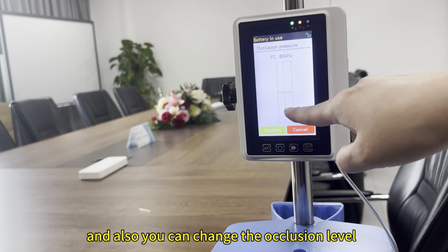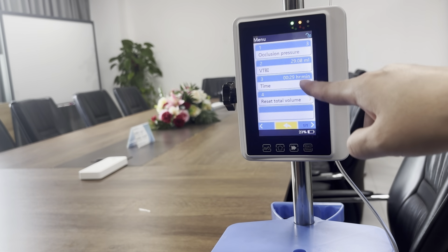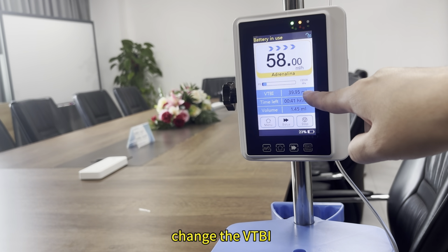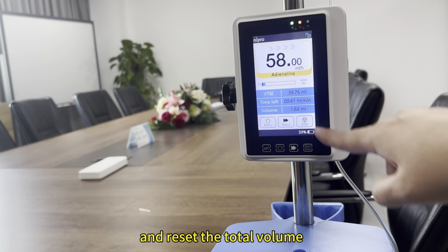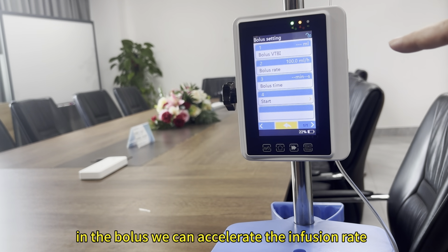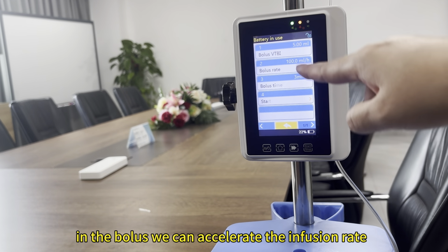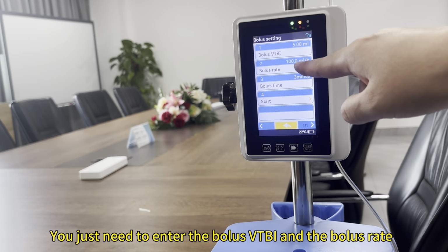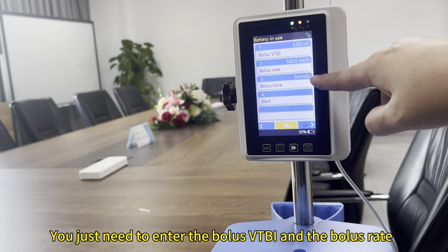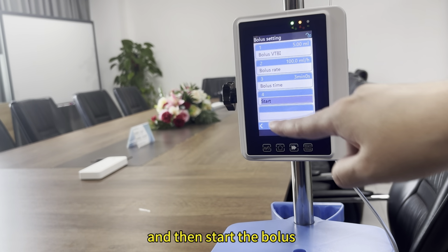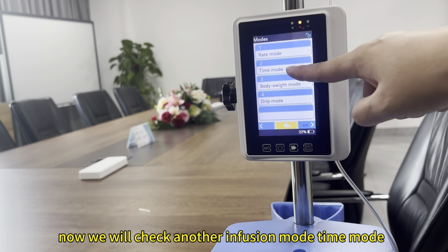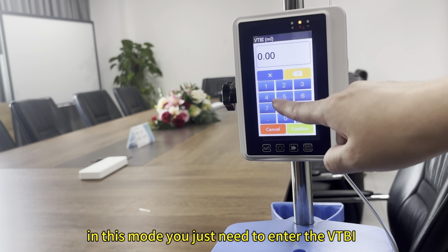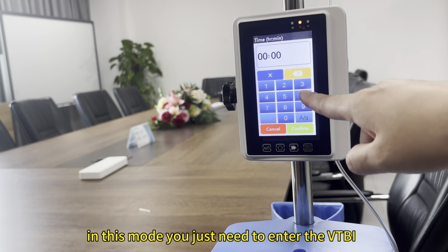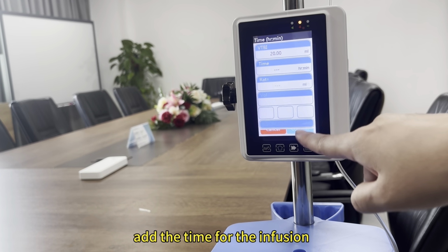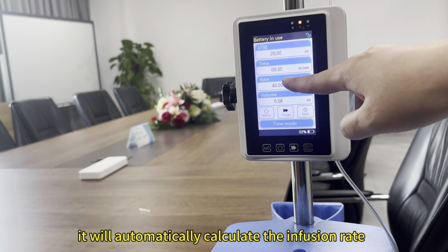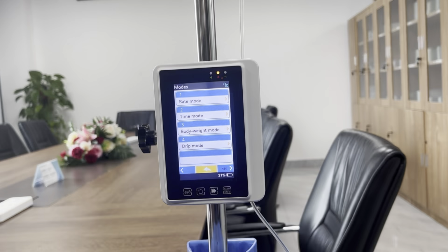And also you can change the occlusion level, change the VTBI, and reset the total volume. In the bolus, we can accelerate the infusion rate. You just need to enter the bolus VTBI and the bolus rate, and then start the bolus. Now we will check another infusion mode, time mode. In this mode, you just need to enter the VTBI and the time for the infusion. It will automatically calculate the infusion rate.